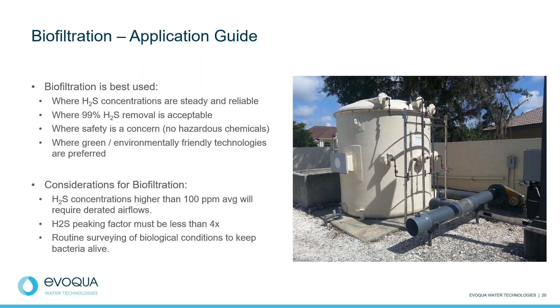be preferred as well. However, we do need to remember that the typical design is based on an average of 100 ppm H2S. So if loadings are greater, we tend to have to derate the airflow from a larger system so that way we can handle the increased sulfide concentration. And then also the hydrogen sulfide concentration should not peak to 4 times greater than the average concentration in order to prevent any kind of odor breakthrough. And then lastly, these systems will require routine surveying of conditions such as airflow, sulfide loadings, pH, nutrient rates, and watering rates to make sure that those bacteria are living in an optimal environment.